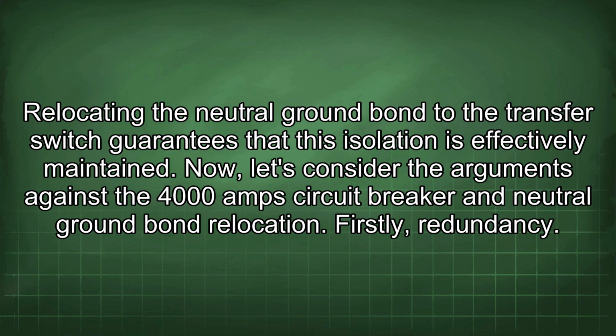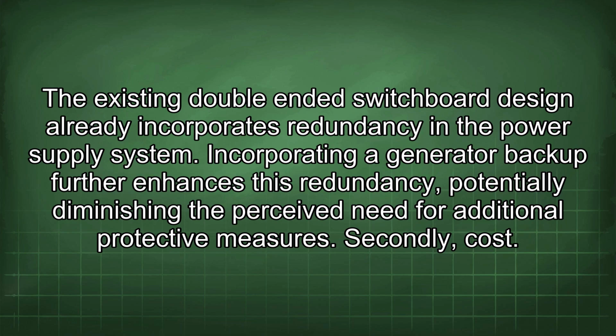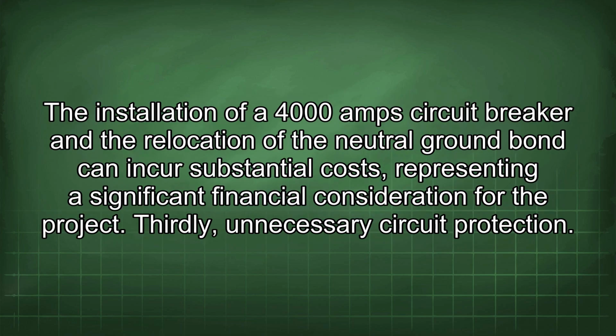Now, let's consider the arguments against the 4000 amp circuit breaker and neutral ground bond relocation. Firstly, redundancy. The existing double-ended switchboard design already incorporates redundancy in the power supply system. Incorporating a generator backup further enhances this redundancy, potentially diminishing the perceived need for additional protective measures. Secondly, cost. The installation of a 4000 amp circuit breaker and the relocation of the neutral ground bond can incur substantial costs, representing a significant financial consideration for the project.